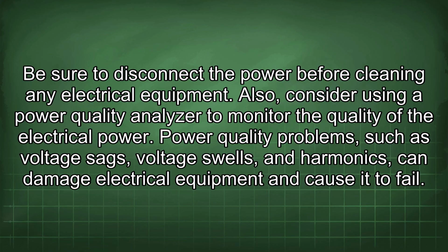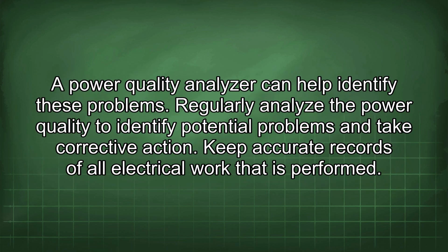Also, consider using a power quality analyzer to monitor the quality of the electrical power. Power quality problems such as voltage sags, voltage swells, and harmonics can damage electrical equipment and cause it to fail. A power quality analyzer can help identify these problems. Regularly analyze the power quality to identify potential problems and take corrective action.